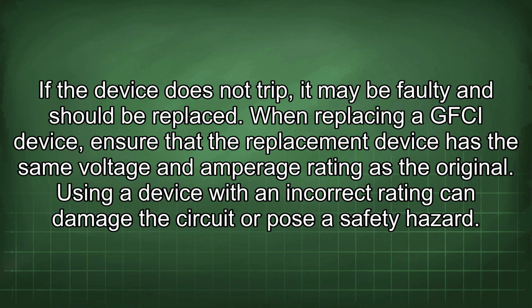When replacing a GFCI device, ensure that the replacement device has the same voltage and amperage rating as the original. Using a device with an incorrect rating can damage the circuit or pose a safety hazard.